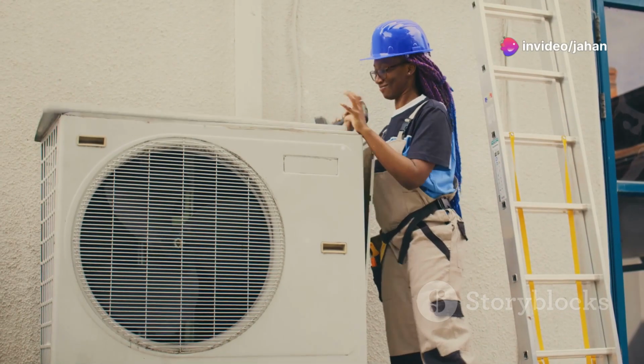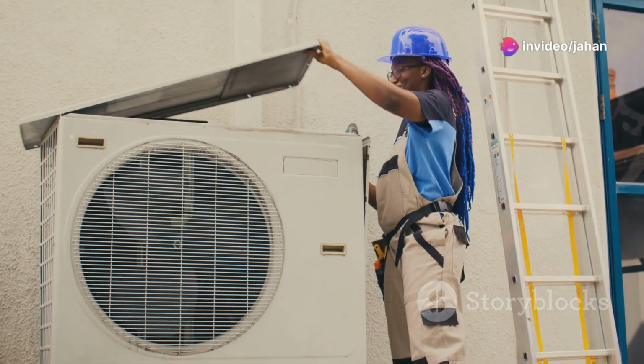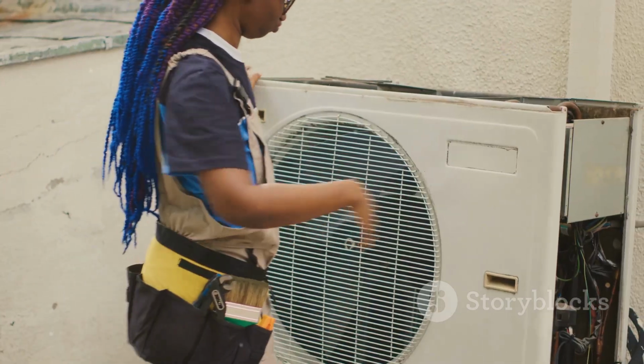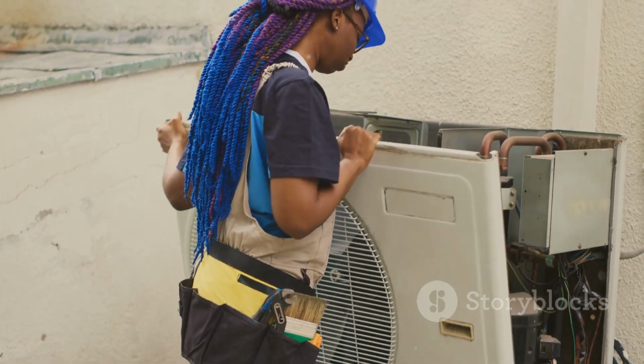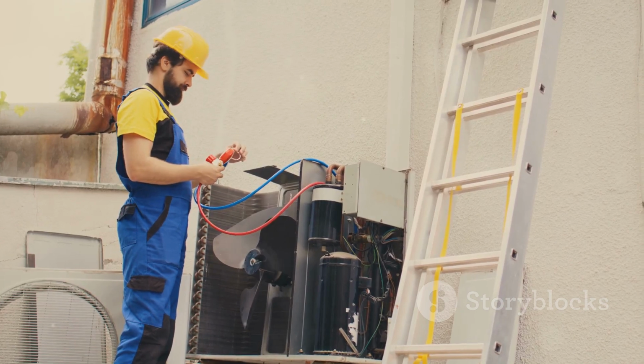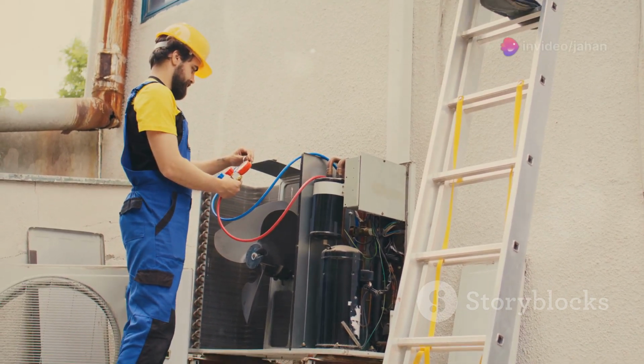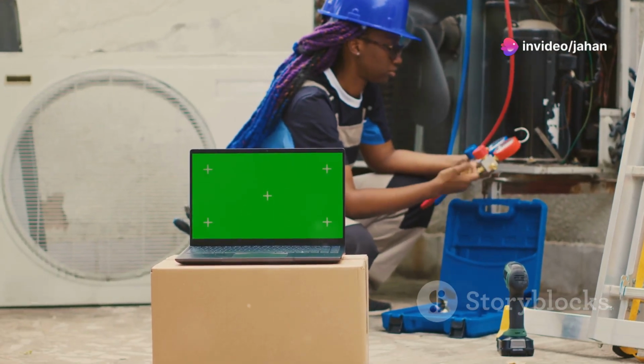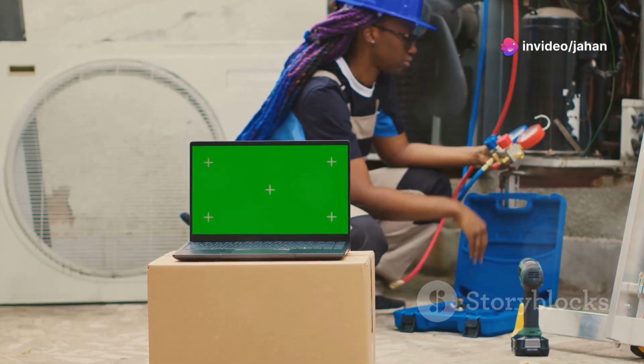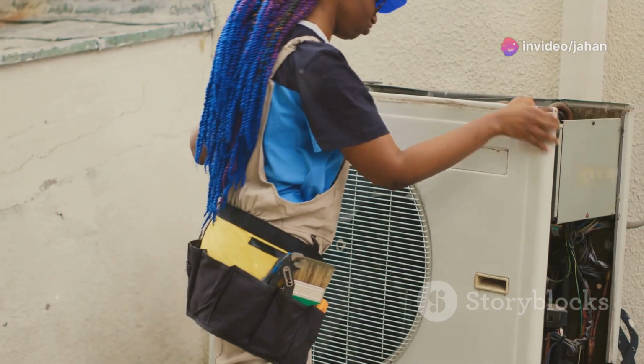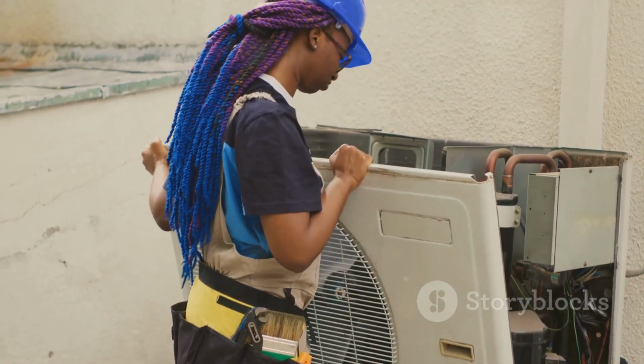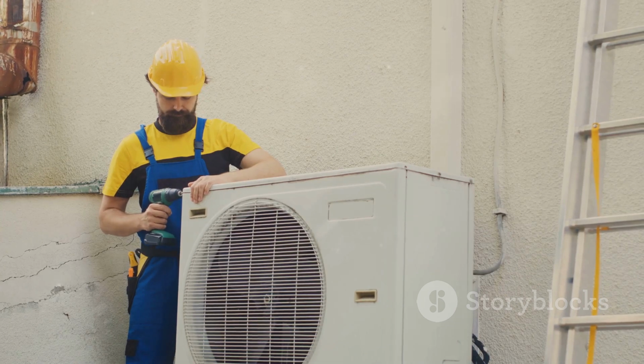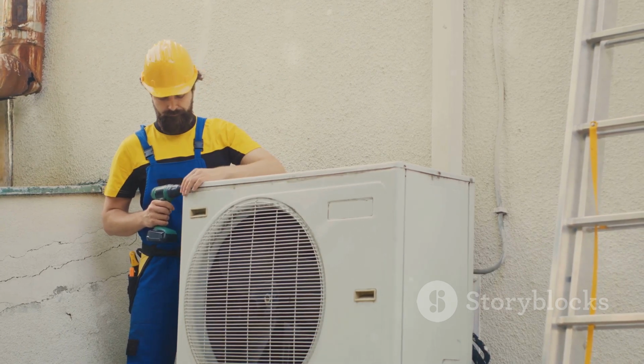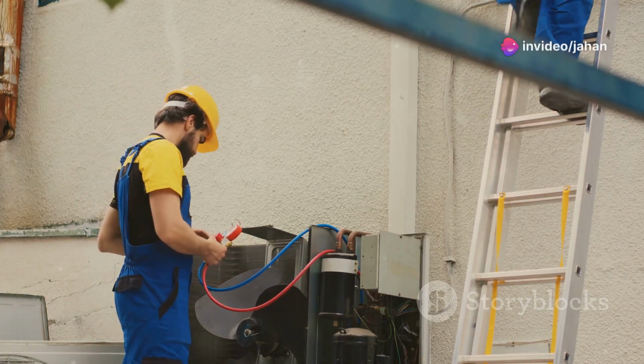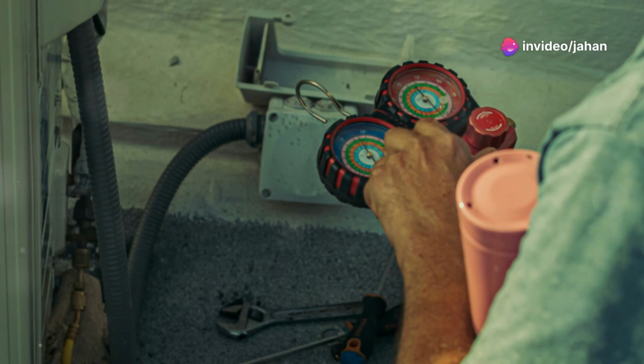Section 5. Recovering refrigerant. Handling it responsibly. Before disconnecting anything, you need to recover the refrigerant. This is a crucial step to protect the environment. Connect the refrigerant recovery machine to the AC unit's service ports. Follow the manufacturer's instructions for your specific machine. The recovery machine will extract the refrigerant from the system. Never vent refrigerant into the atmosphere. It's illegal and harmful to the ozone layer.